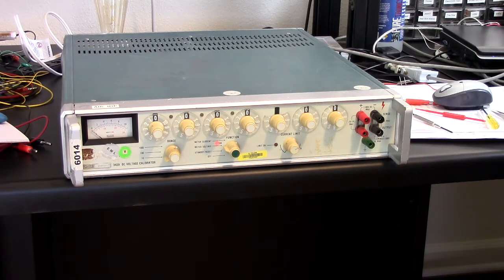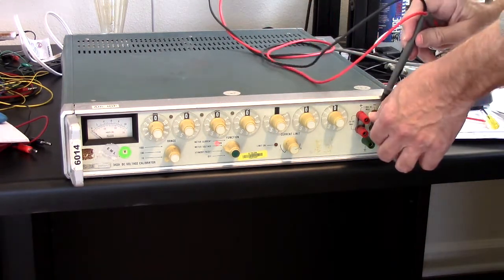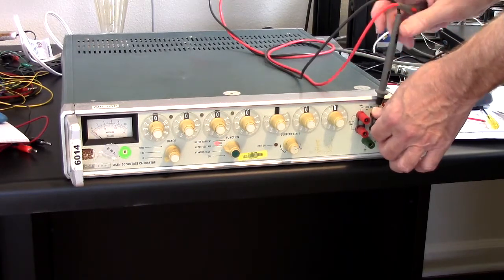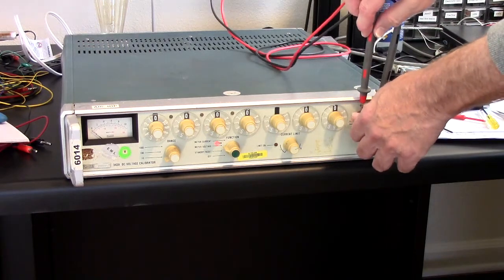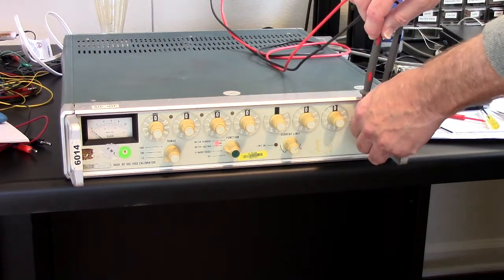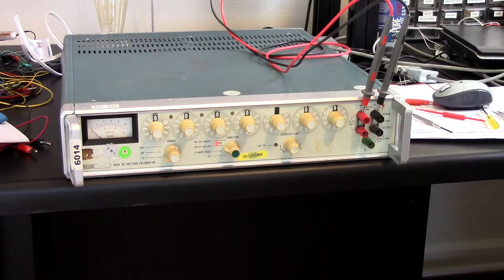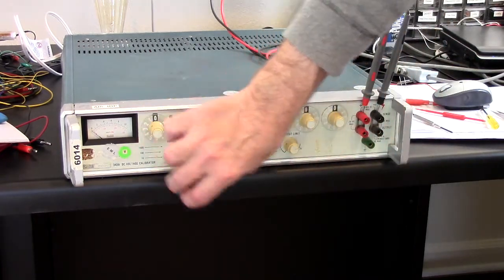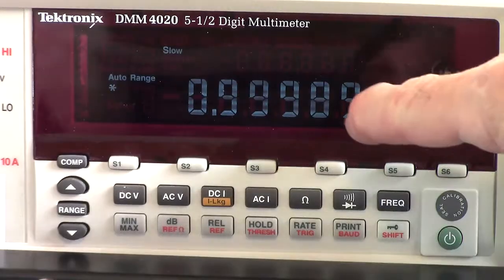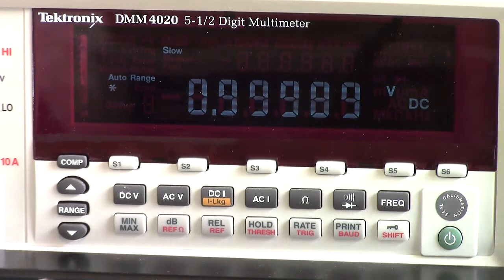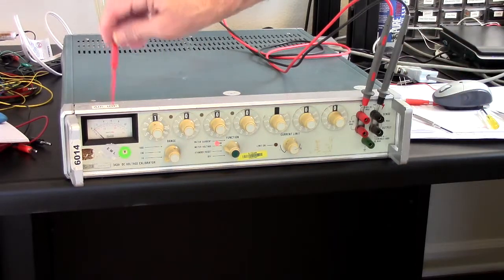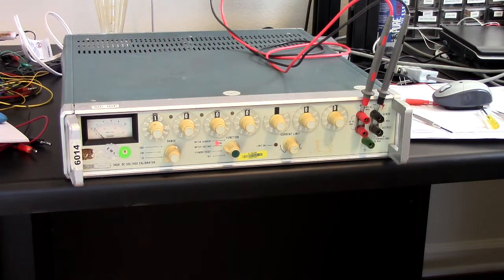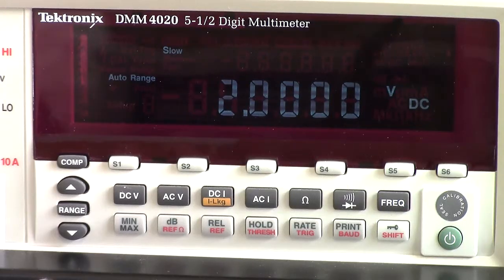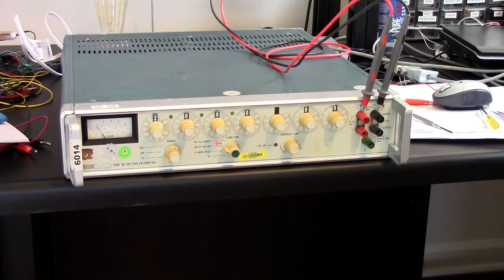I'm going to hook it up to the voltmeter. Now this is my Tektronix DMM 4020, which has been recently calibrated. It's only 5.5 digits. I'm on the 10 volt scale, so let's give it 1 volt. 0.999989, and I've just turned it on, so it hasn't had a chance to warm up and stabilize. Did the meter do anything? Yeah, it moved a little bit. That's a positive sign. That's pretty close to 1 volt. 2 volts. 2.0, within one count there.